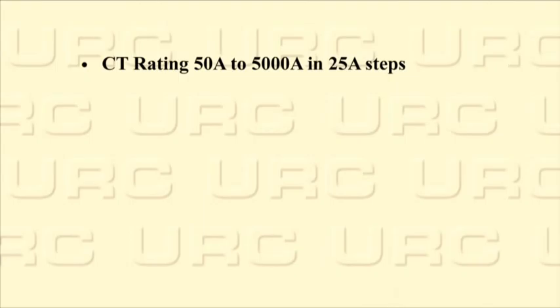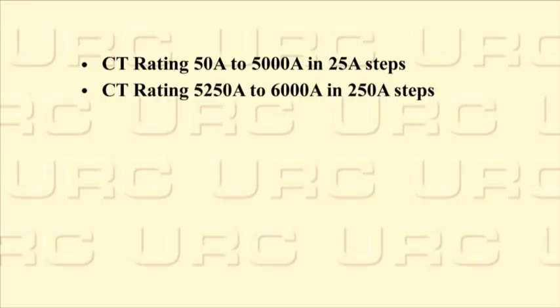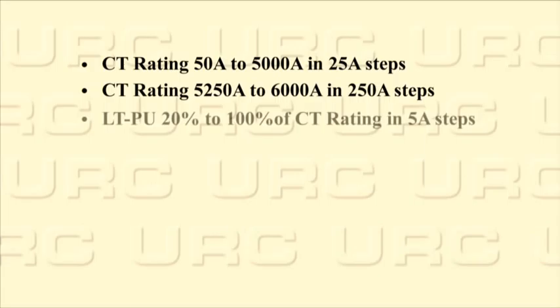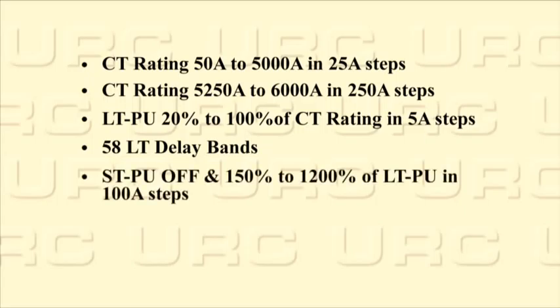The CT rating can be set from 50 to 5,000 amps in 25 amp steps, and 5,250 to 6,000 amps in 250 amp steps. The long time pickup can be set from 20% to 100% of the CT rating in 5 amp steps. The long time delay has 58 time band settings. The short time pickup can be set from 150% to 1200% of the long time pickup setting in 100 amp steps. An off setting is available as long as instantaneous is not set to off.